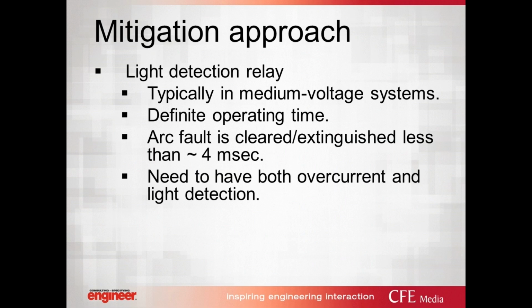Continuing on mitigation approaches, this is the last one I have: light detection relay. Again, this is another one that is becoming popular, typically applicable mainly in medium voltage systems. There is a definite operating time, and the arc fault can be cleared and extinguished in less than around 4 milliseconds, though that's just a bulk number and may differ. You need to have both overcurrent and light detection to operate and detect.